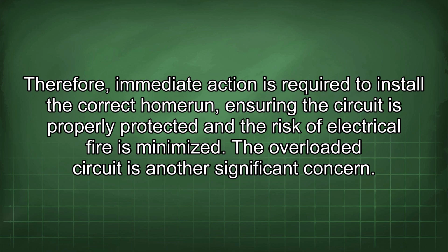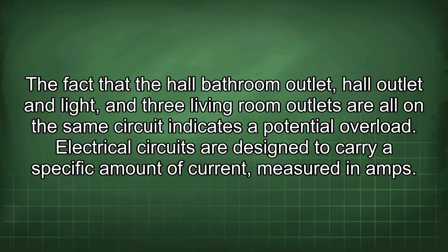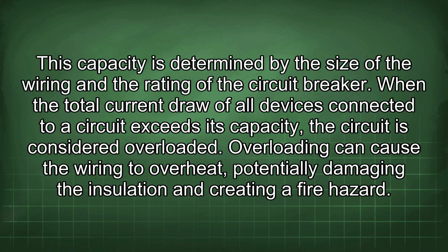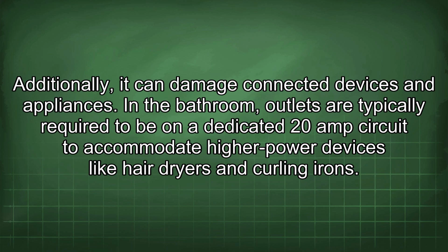The overloaded circuit is another significant concern. The fact that the hall bathroom outlet, hall outlet and light, and 3 living room outlets are all on the same circuit indicates a potential overload. Electrical circuits are designed to carry a specific amount of current, measured in amps. This capacity is determined by the size of the wiring and the rating of the circuit breaker. When the total current draw of all devices connected to a circuit exceeds its capacity, the circuit is considered overloaded. Overloading can cause the wiring to overheat, potentially damaging the insulation and creating a fire hazard. Additionally, it can damage connected devices and appliances.